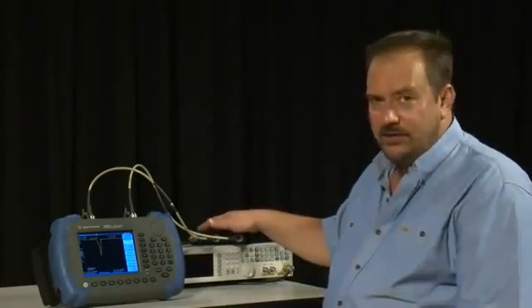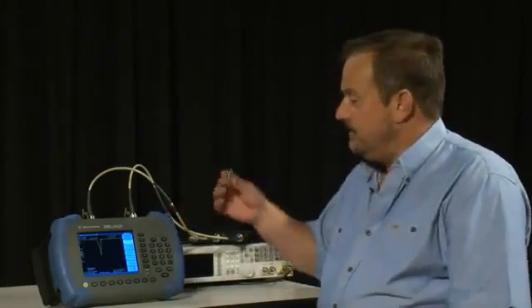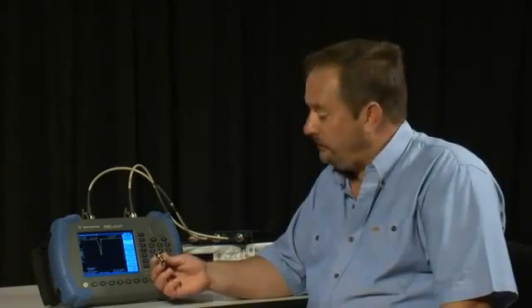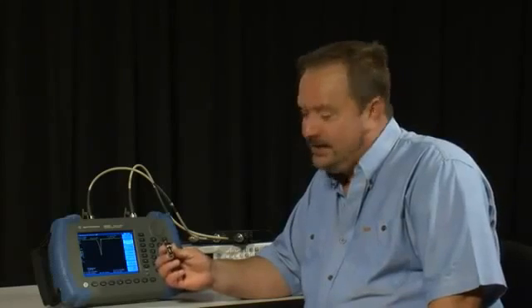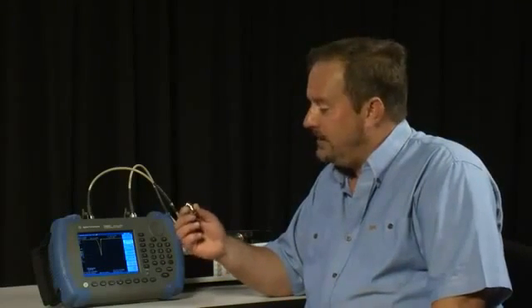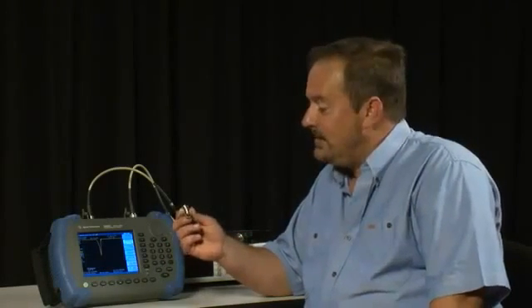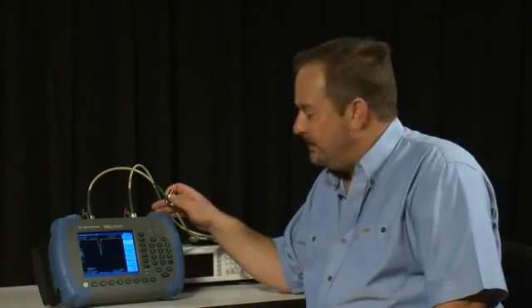Now those of you that have done network analyzer measurements before will know that we are never making an absolute measurement of a device. We are always making a relative measurement, comparing the frequency response of this filter with a known standard. In this case, I am going to use a type N through bullet adapter. And this is a good opportunity to point out that for making network analyzer measurements, the quality of your measurement is going to depend very much on the quality of the adapters that you use. So rather than getting a cheap one from the local electronics store, I spend a bit more money and go and get a good quality one that you keep with the instrument for this kind of measurement.